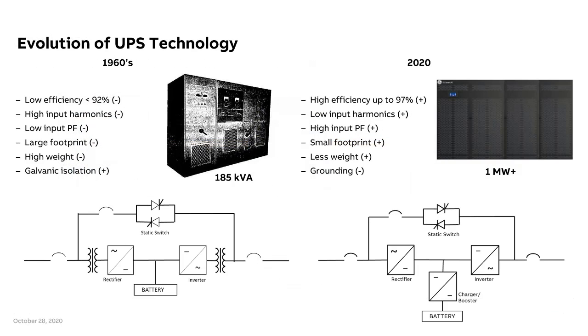Moving on just quickly through the next couple of slides. I mentioned the double conversion UPS as we know it has been around, it's coming up on its 60th birthday. The picture on the left part of the slide here is relevant to my background, but also the current. That's actually a GE UPS from the early 60s, SCR based, on GE thyristors or SCRs. And then the product on the right side is a modern one megawatt UPS. The 1 megawatt is probably more compact than the 185 from 60 years ago. The single line is very similar though.